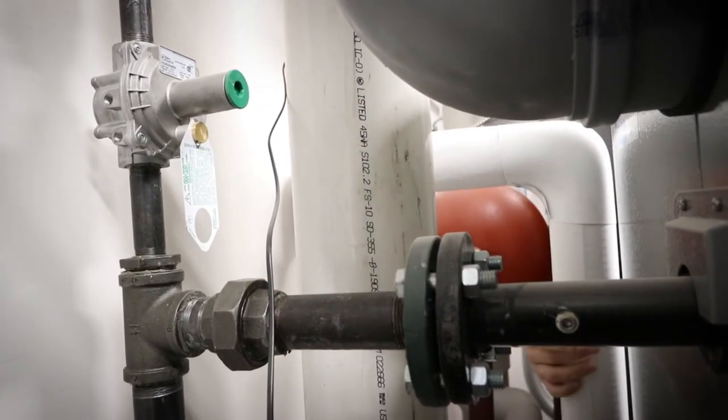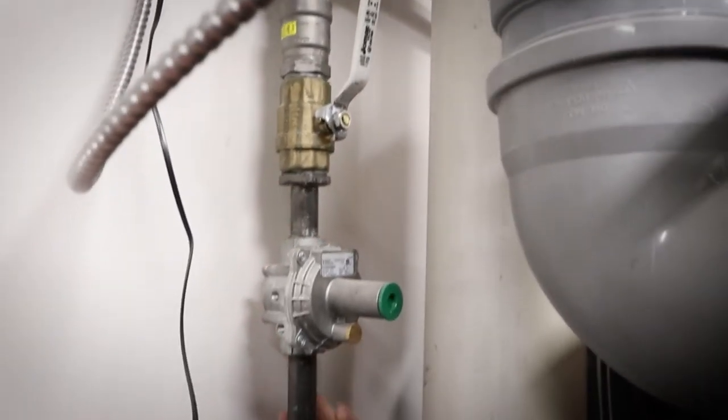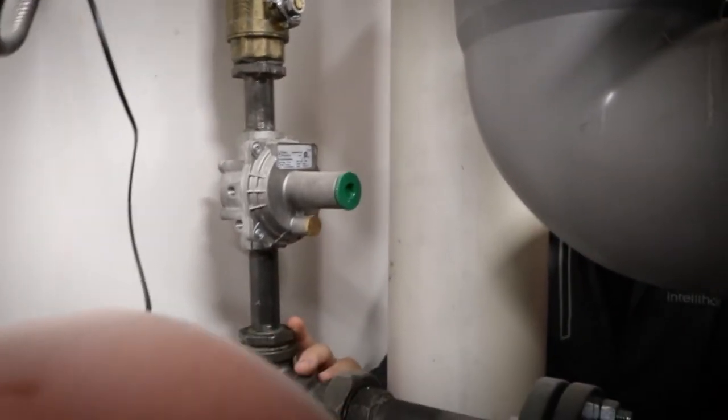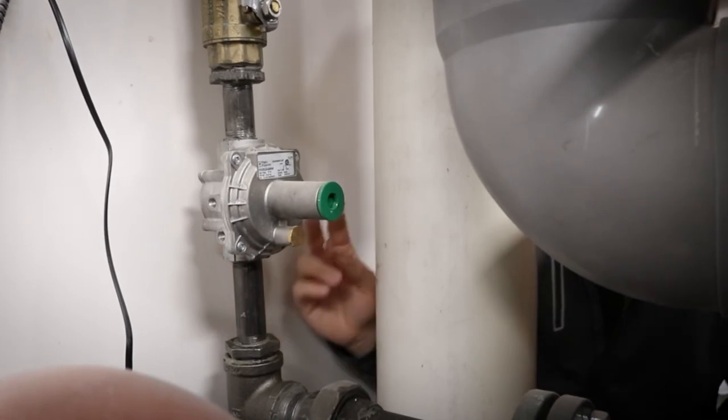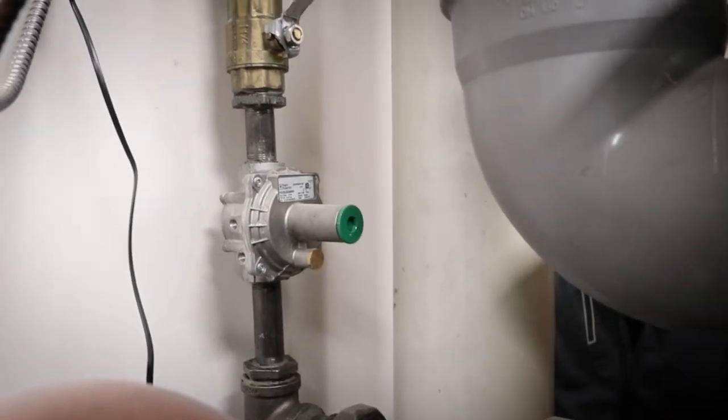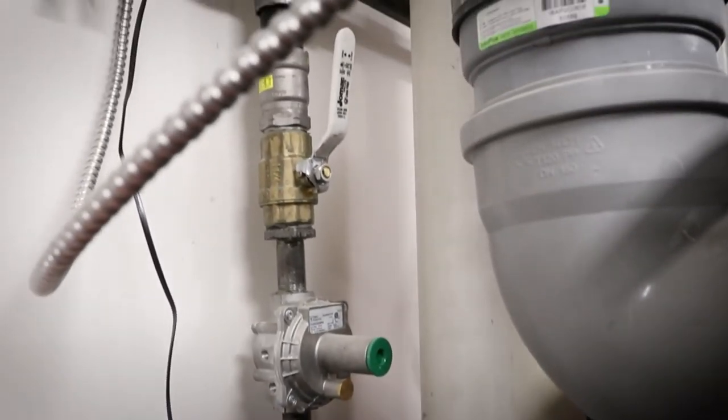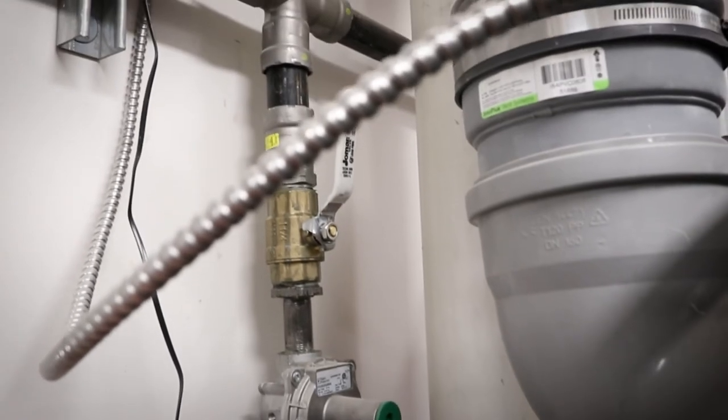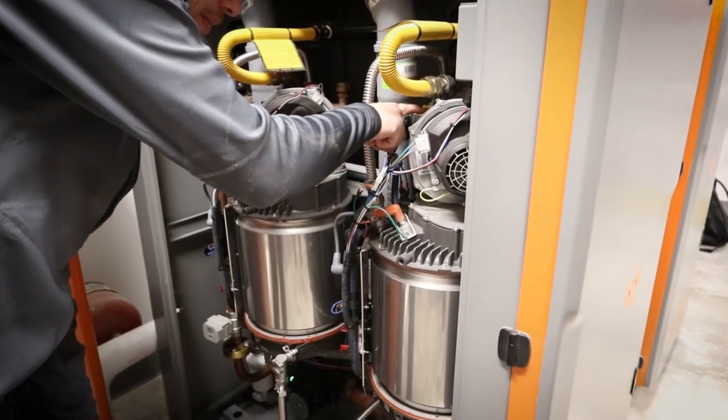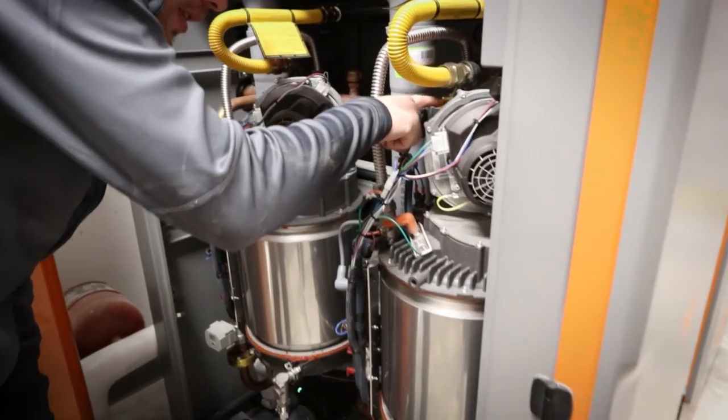Size the gas regulator based on the BTU rating of the unit and install it per the manufacturer's requirements. Use the gas regulator to set the gas pressure at 8 inches of water column for a natural gas unit and 11 inches of water column for a propane unit if possible. When setting the gas pressure, ensure at least one heat exchanger is firing.